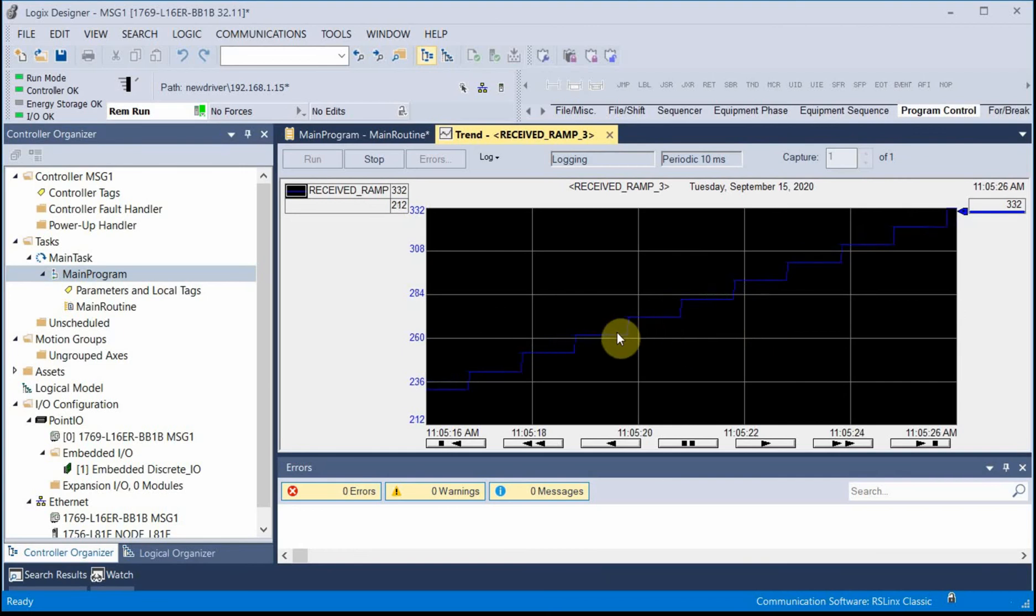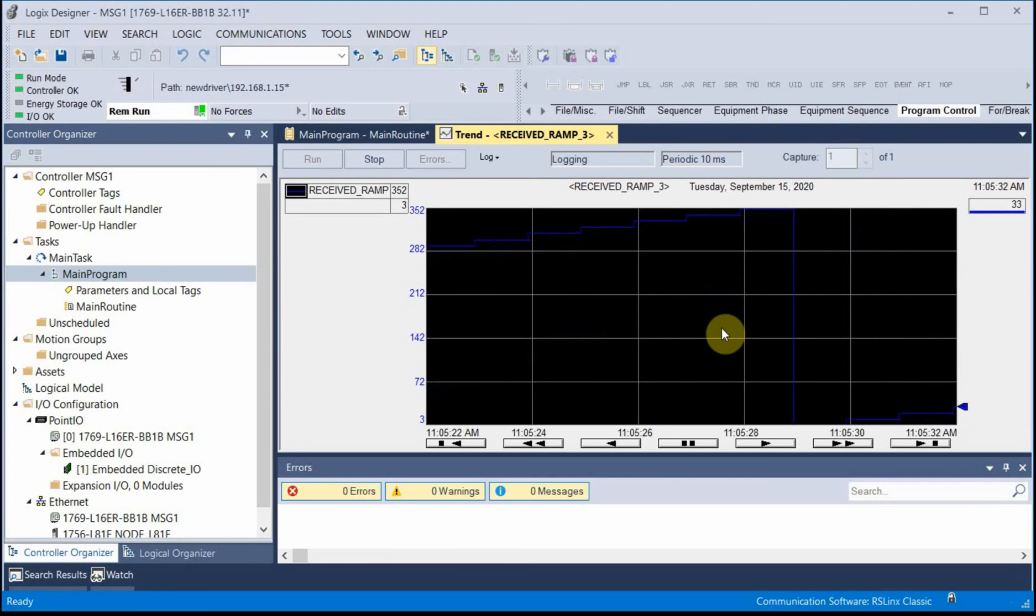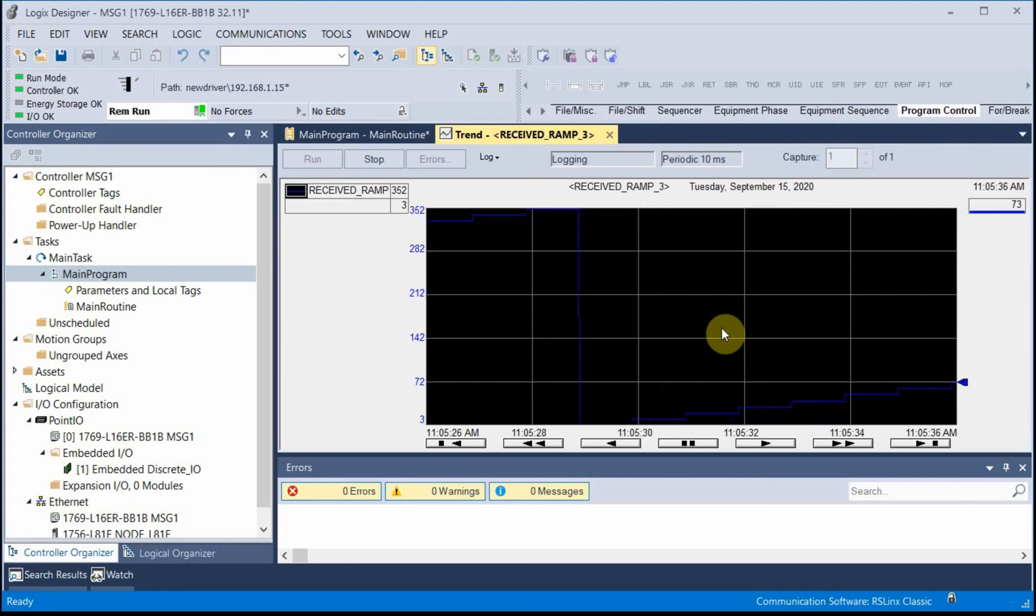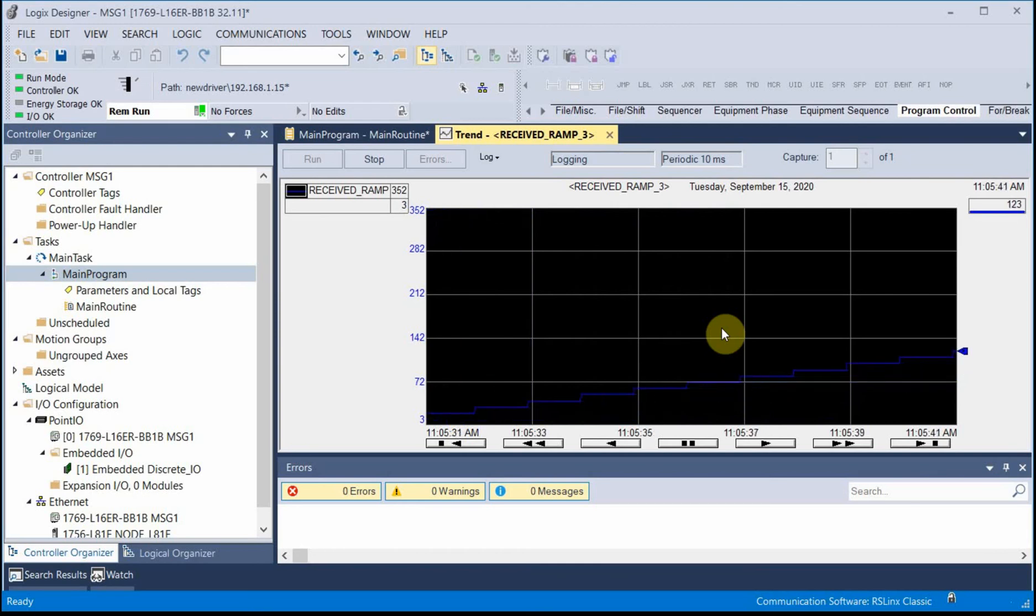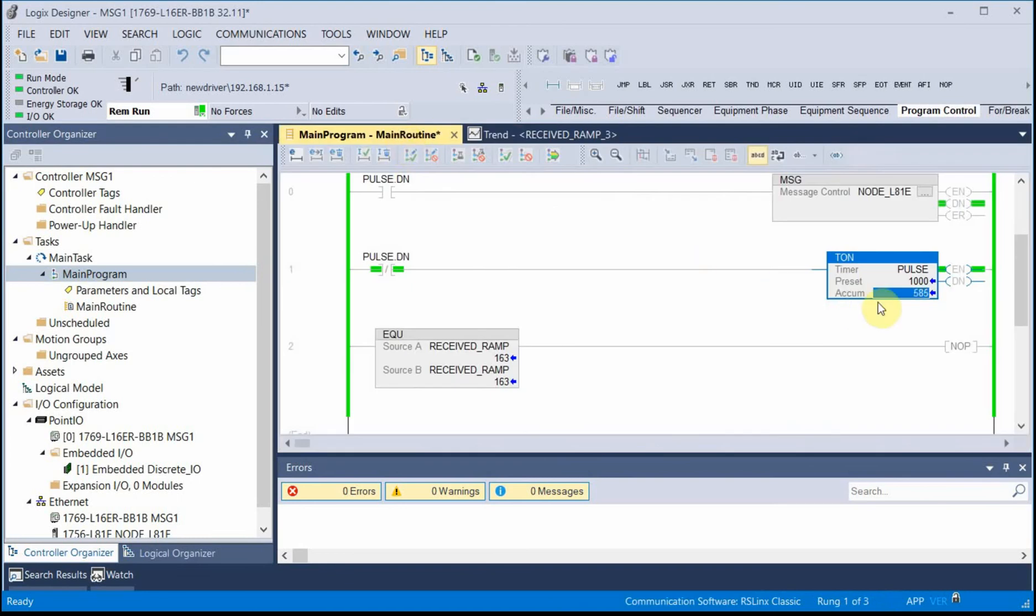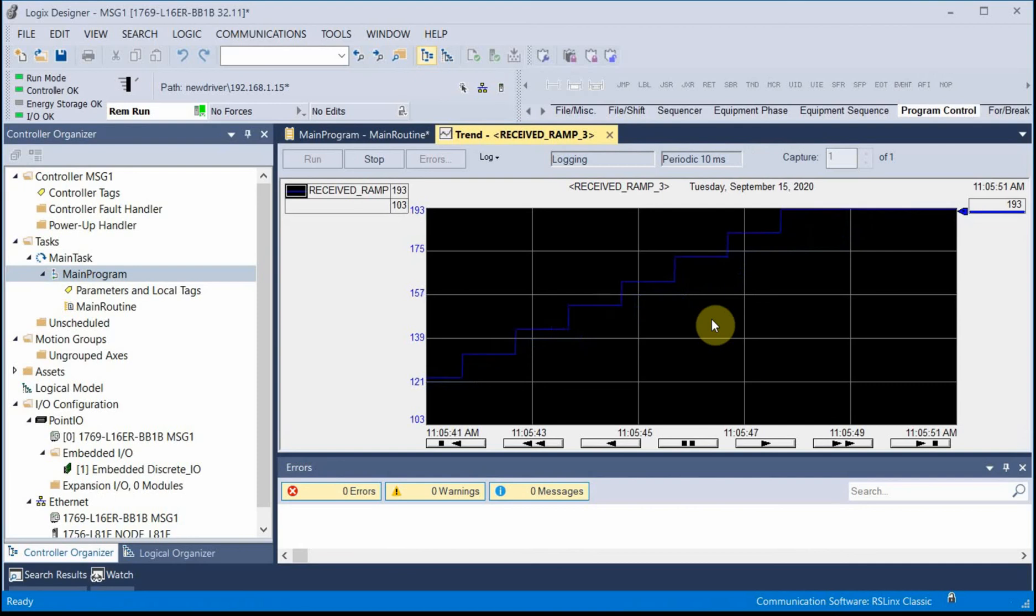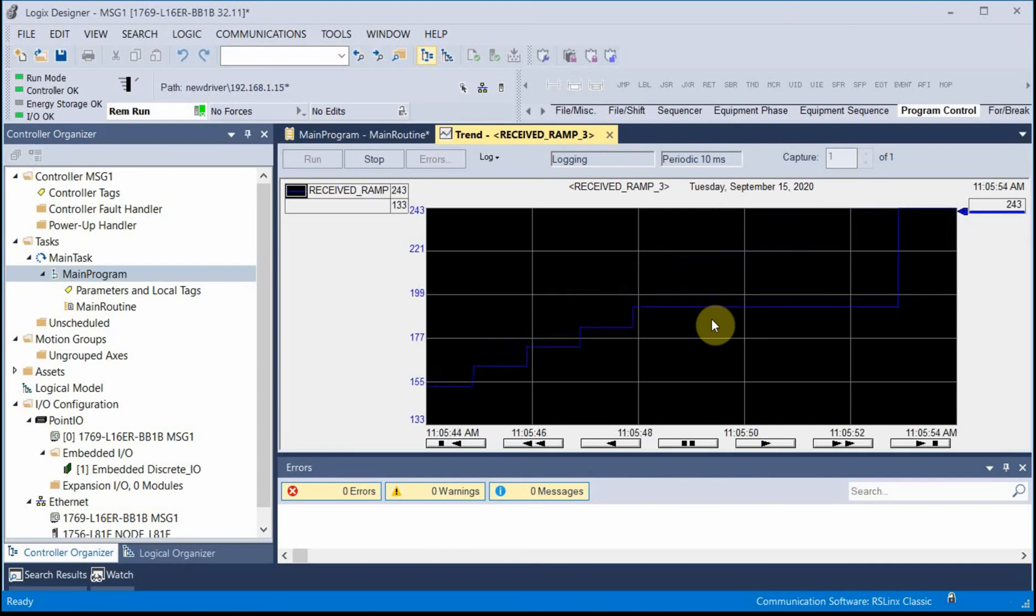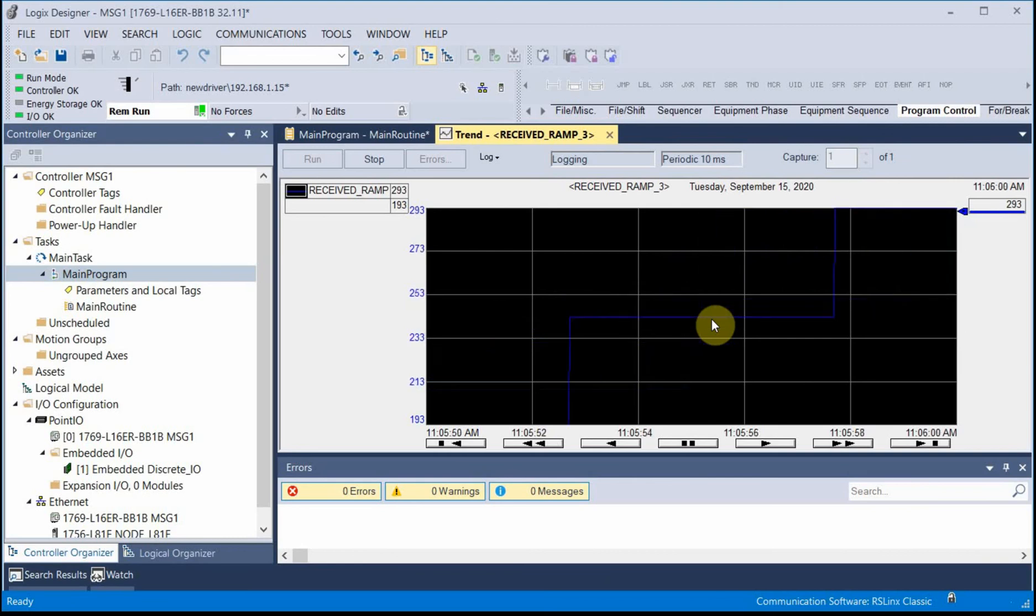And I think now I'm getting some irregular data. It looks like I'm counting every other pulse. Now it's important to know that the messaging instruction is asynchronous. I ask it to message. It goes through a series of changes with the remote controller. And I get a number back. So if my sampling rate is too slow, let's go every five seconds. What I'll see is my data will jump in huge increments like that. It's no longer really close to real time.